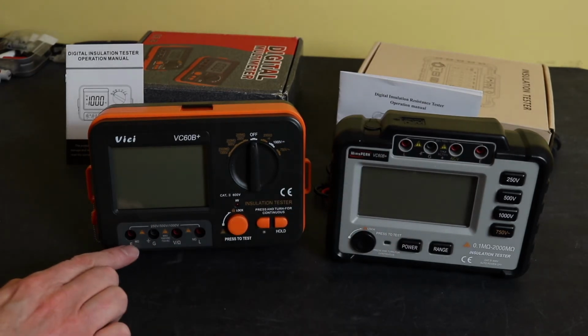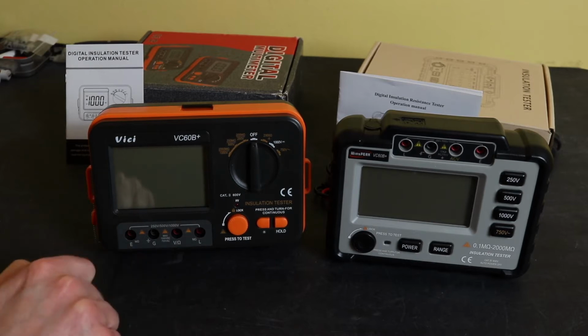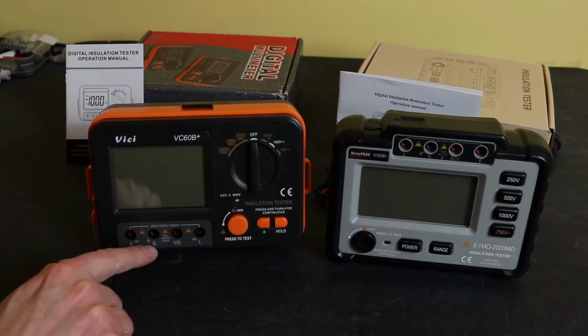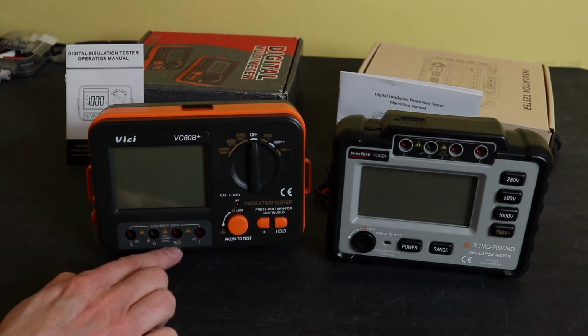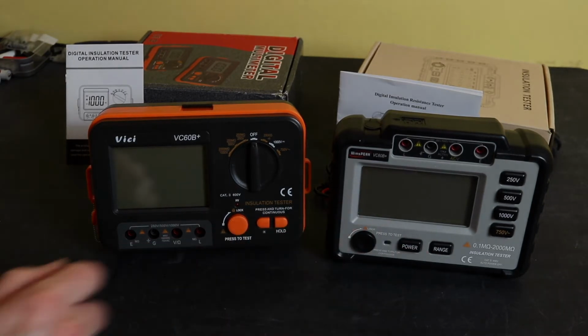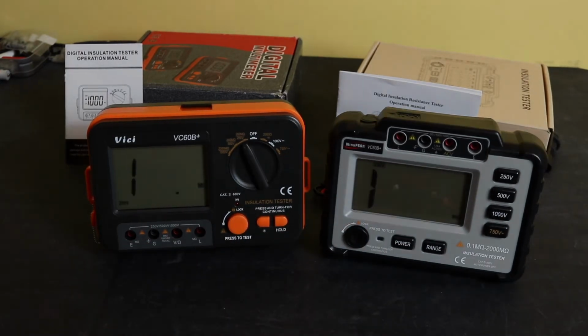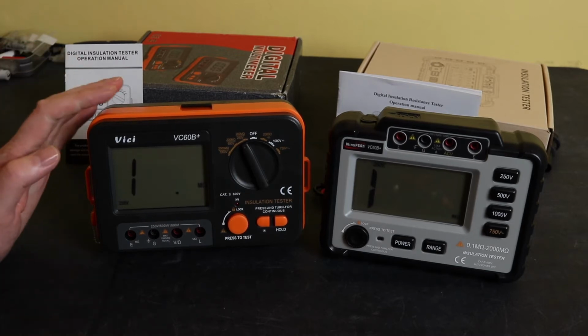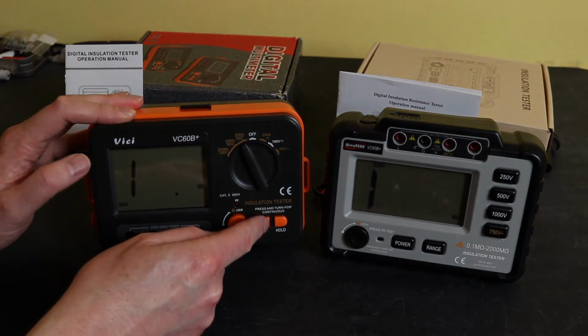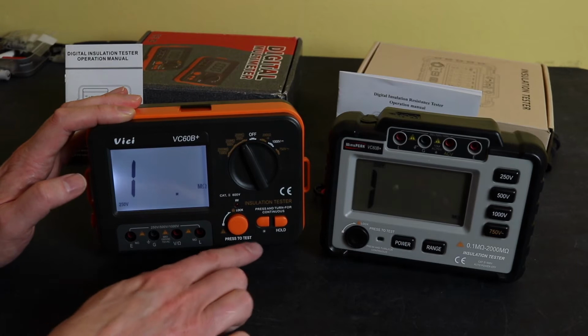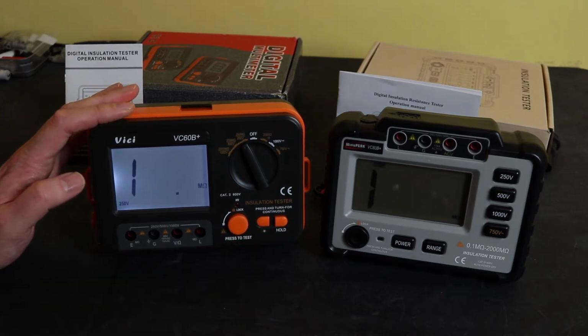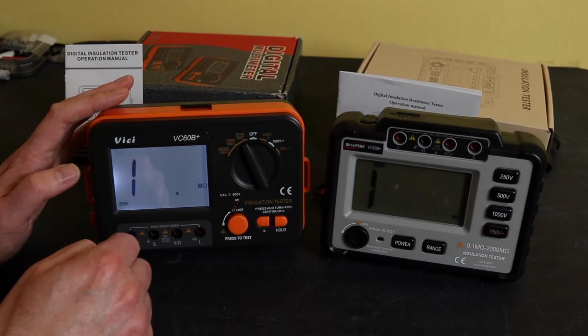They both, for insulation testing, use the E and the L connections. You also have a guard terminal here, which is interesting. It's not usual to have a guard terminal on a low voltage insulation tester, so we'll test that out later. And then you have to change position for the volts and ohms reading, or just the AC volts on that unit there. So you can see here both the units switched on to the 250 volt test function. The Vici unit here, you can press the button in to bring the light on, and that stays. It's a push to hold button, so it stays until you press it again to take the light back off.